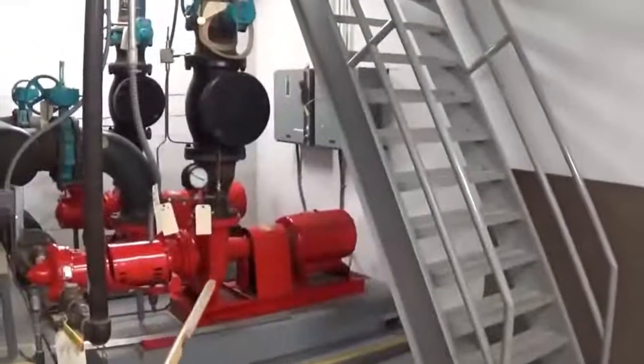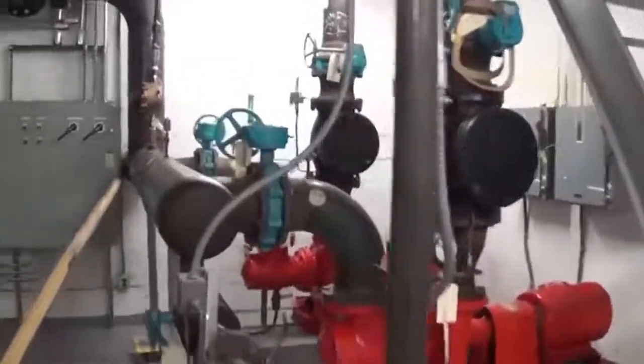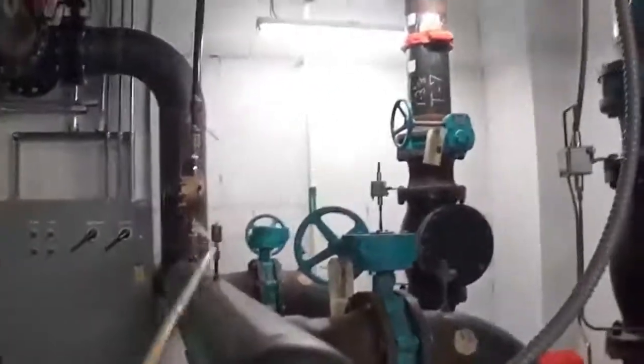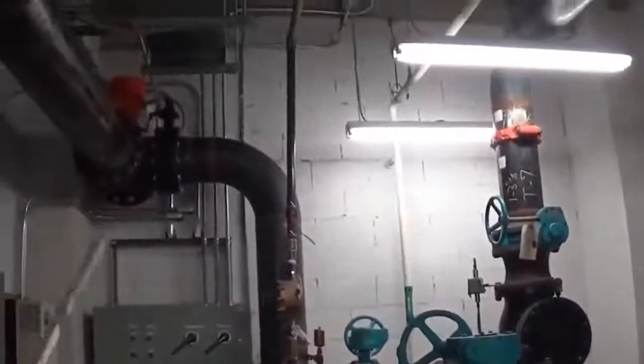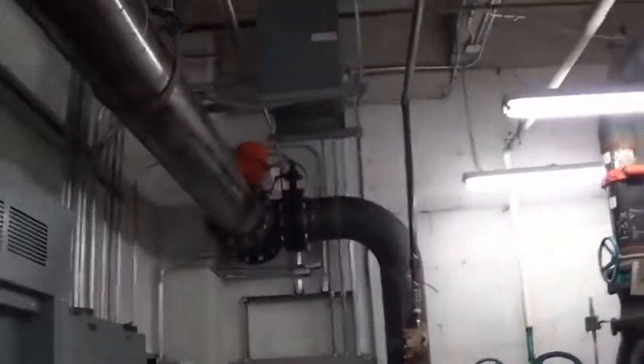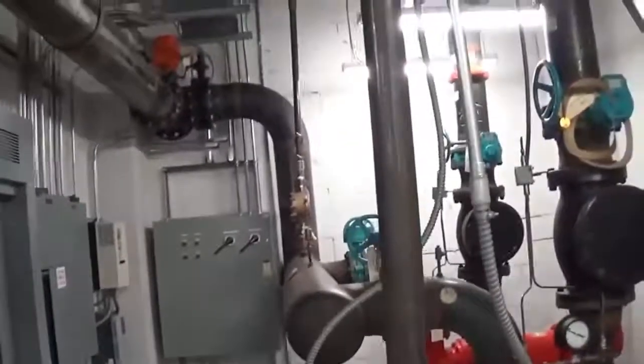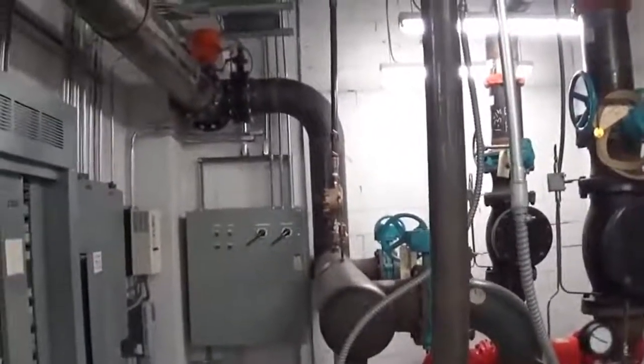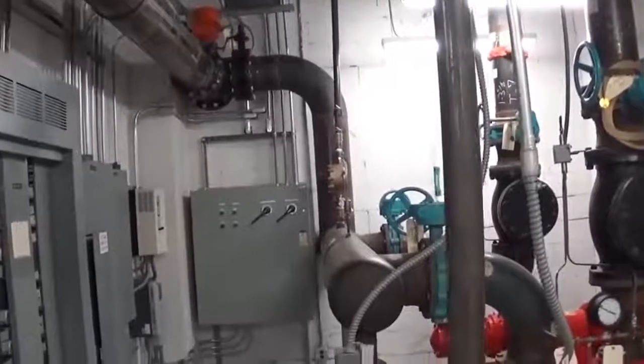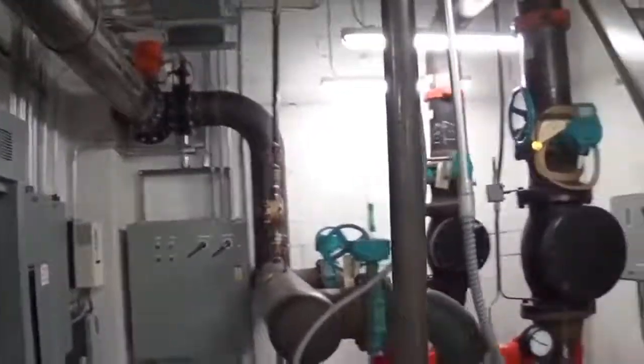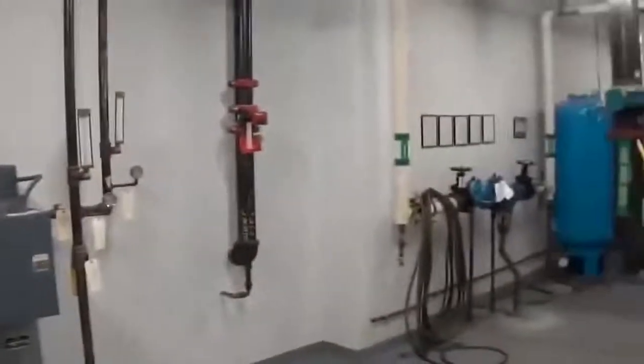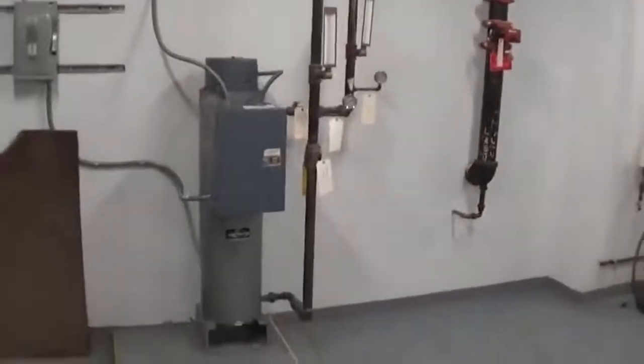So here comes the warm water in the condensing loop. It goes to these pumps, and then it leads to outside where there's a cooling tower sitting on the outside. And the cooling tower is a large reservoir, and it has fans at the top of it, and the fans reject the heat into the atmosphere. We'll take a walk out there. It's kind of dark and cold today, but we'll do the best we can.